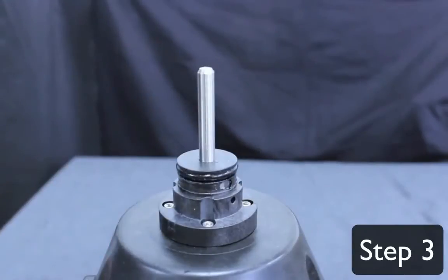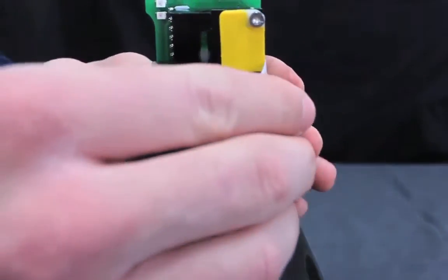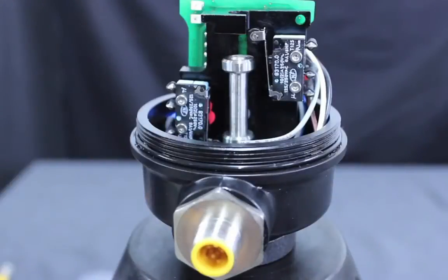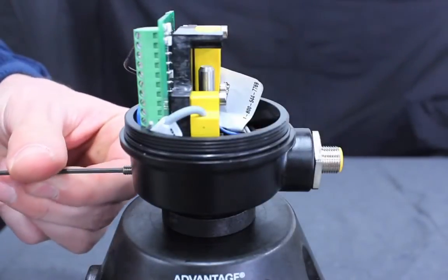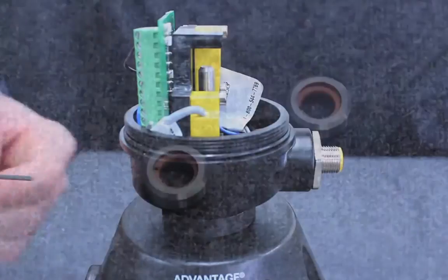Step 3: Install the lower switch housing assembly onto the pedestal. Make certain the housing is completely seated on the pedestal shoulder. Pictured here is the mechanical switch option, the main difference featuring the lever arm. All steps are followed the same for both models. Use a 5/64 inch hex Allen key to tighten the lower switch housing set screw firmly. Do not over-tighten.